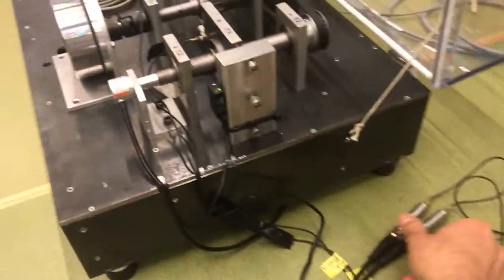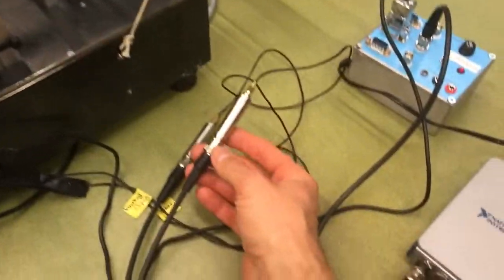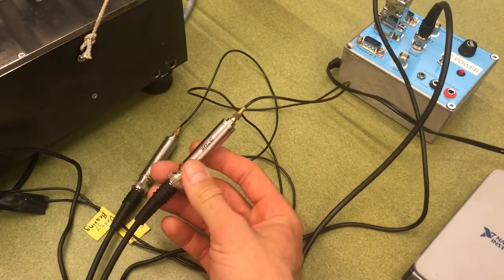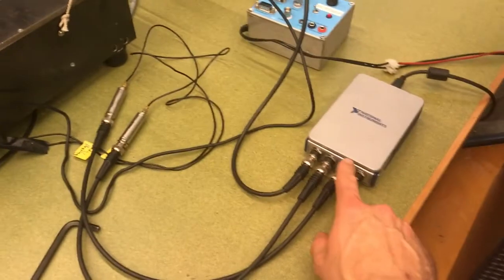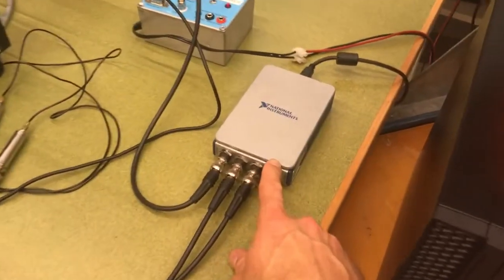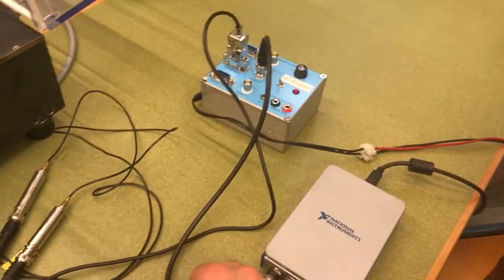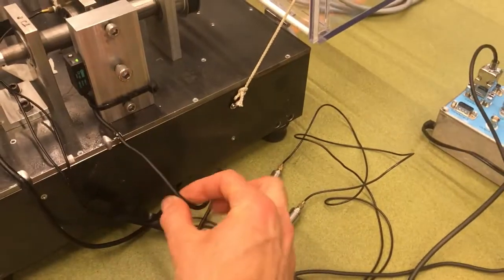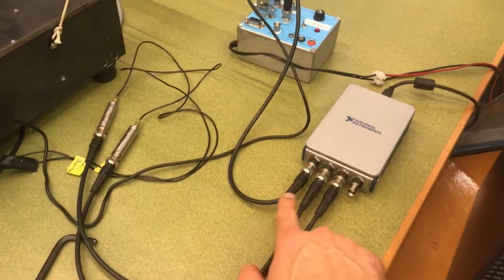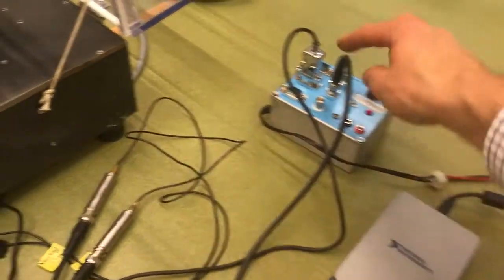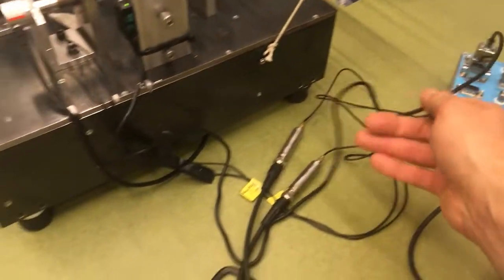The instruments are powered, accelerometers are powered by these inline charge amplifiers here which are provided with constant current from the data acquisition system here, National Instruments Data Acquisition System. The tachometer is powered using this DC power supply over here, so tachometer signal comes again into the acquisition system on that channel and this cable goes to the tachometer.